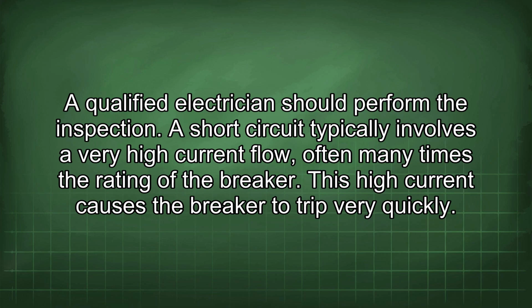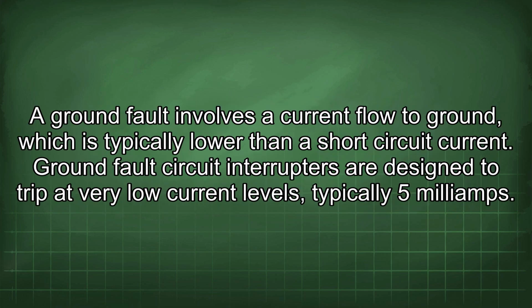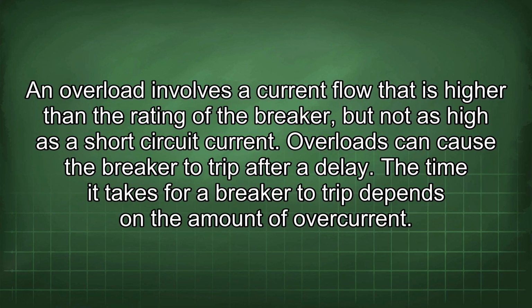A short circuit typically involves a very high current flow, often many times the rating of the breaker. This high current causes the breaker to trip very quickly. A ground fault involves a current flow to ground, which is typically lower than a short circuit current. Ground fault circuit interrupters are designed to trip at very low current levels, typically 5 mA. An overload involves a current flow that is higher than the rating of the breaker, but not as high as a short circuit current. Overloads can cause the breaker to trip after a delay. The time it takes for a breaker to trip depends on the amount of overcurrent.